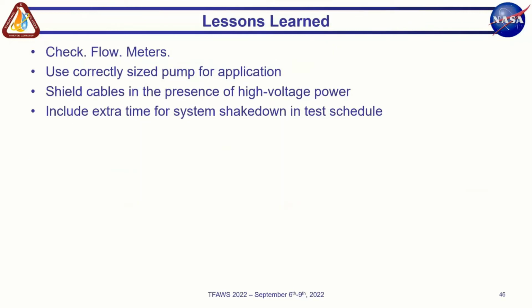Lessons learned, always check your flow meters, always check your instrumentation. We had a few issues during collection because of malfunctions with some of our instrumentation. Definitely always use a correctly sized pump for your applications. Make sure you're shielding cables in the presence of high voltage power, and always include extra time, more time than you think you need for a system shakedown in your test schedule.